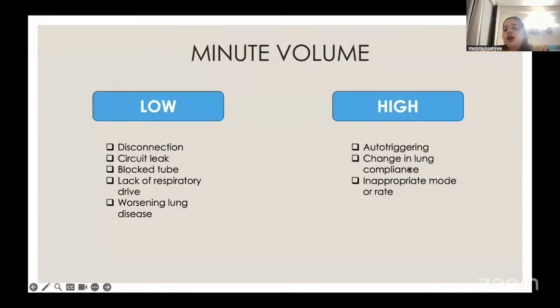There was a stiff lung. It was requiring very high pressures to reach a tidal volume. And now we gave surfactant and the lung compliance improved. So now the set pressures are too high for the baby and there would be a high minute volume alarm. Or thirdly, there has been an inappropriate mode or rate. So here the baby is fairly okay, so we do not have to support every breath, which might be happening in this case.